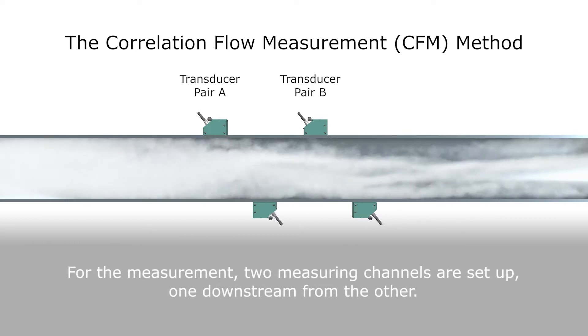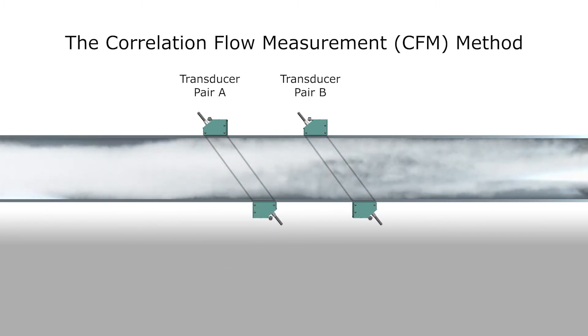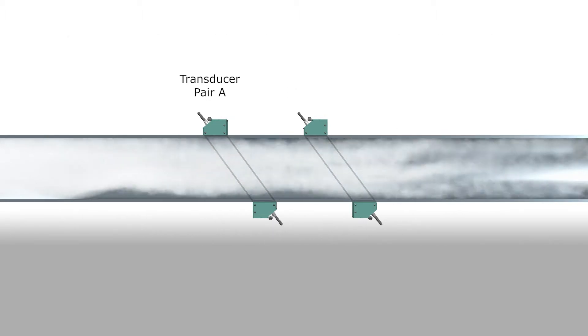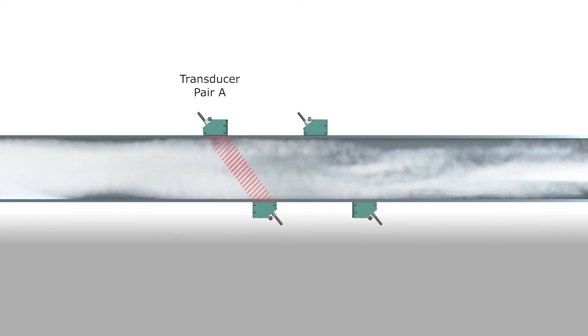Two pairs of transducers are attached non-invasively to the exterior of the pipe. Each pair consists of two transducers precisely positioned opposite each other on opposing sides of the exterior walls, forming a diagonal channel. The transducer pairs are spaced at a mutual distance Delta X. The top transducer in pair A continuously emits ultrasonic signals through the pipe and the fluid towards its paired opposite transducer below.